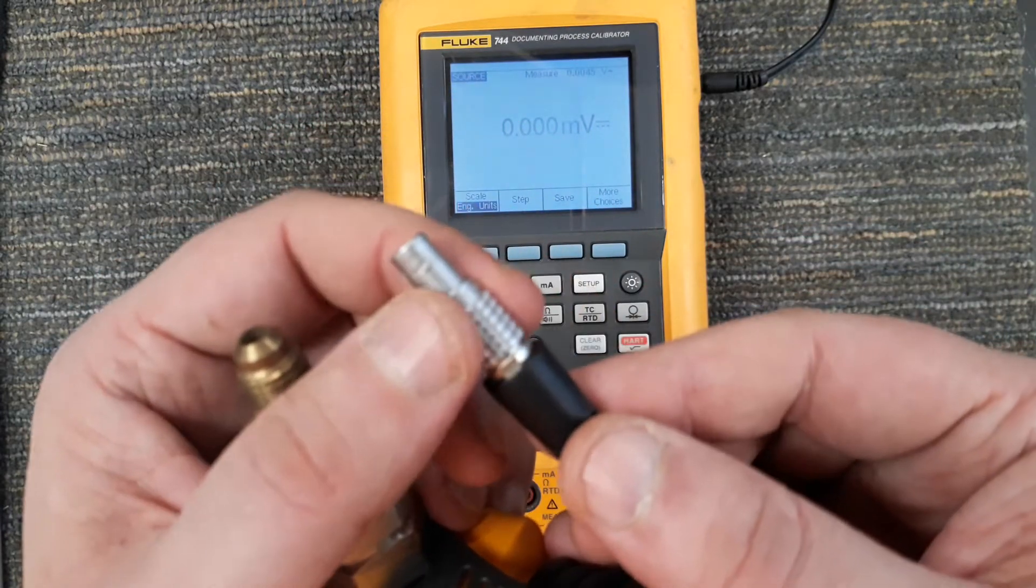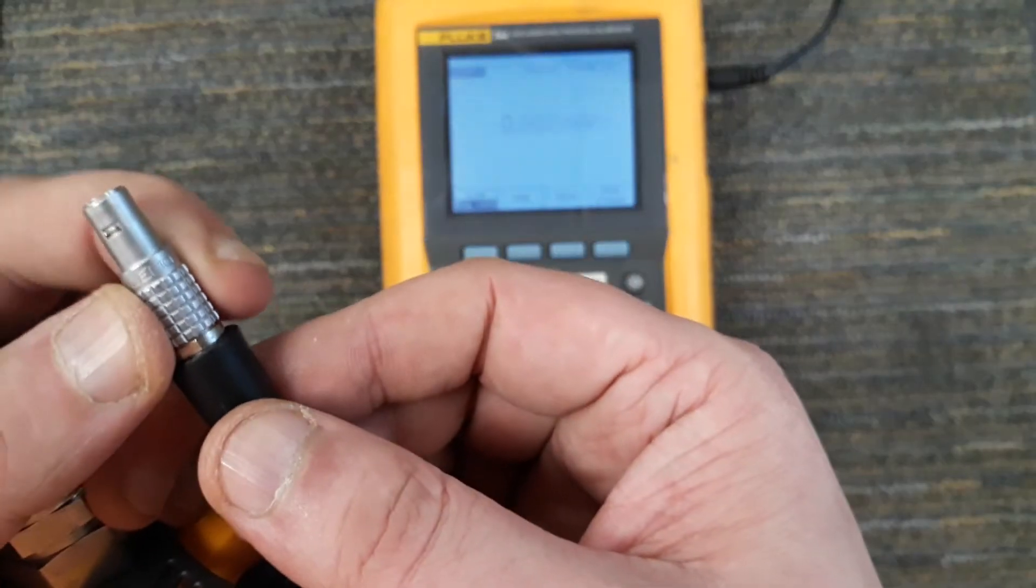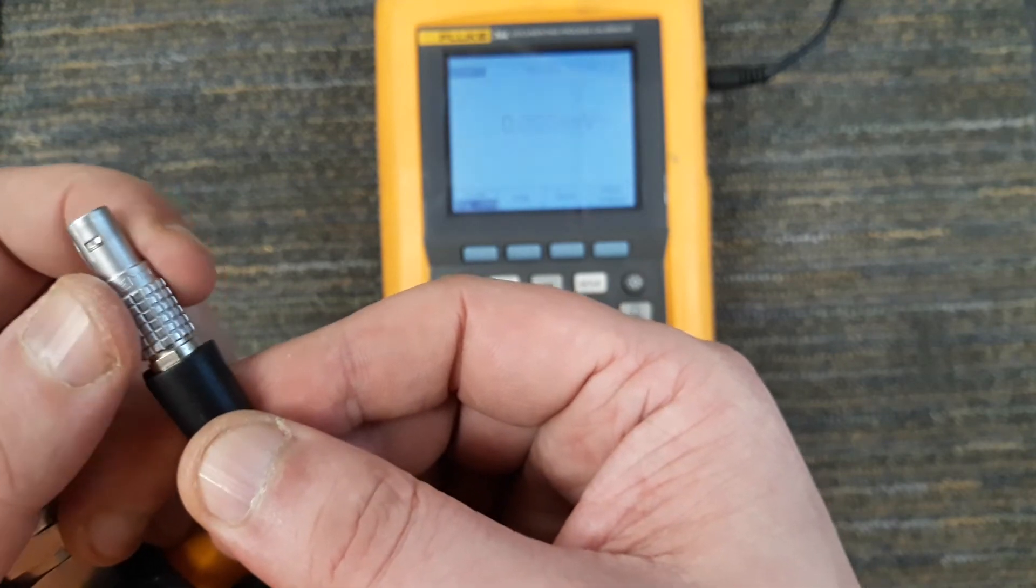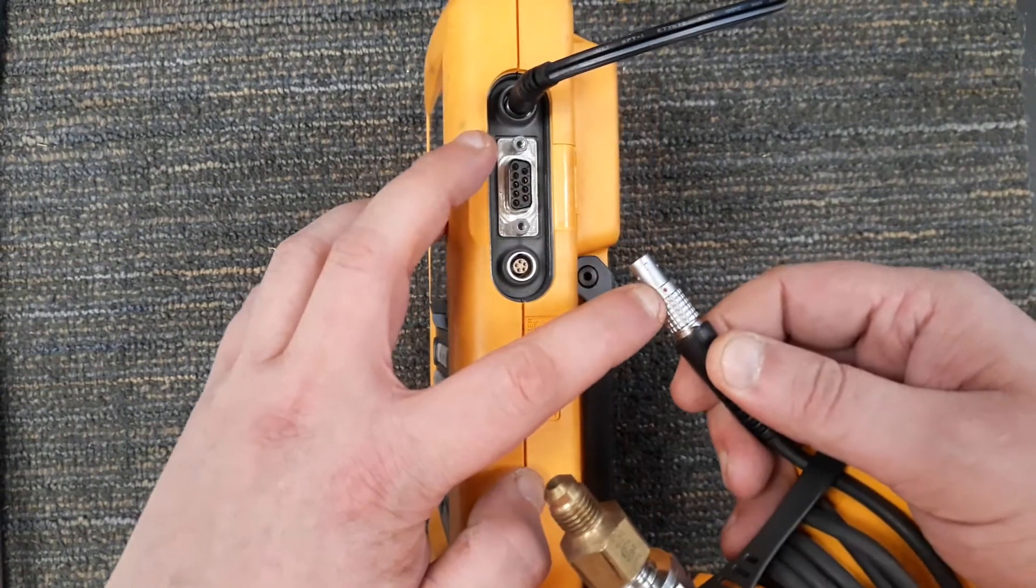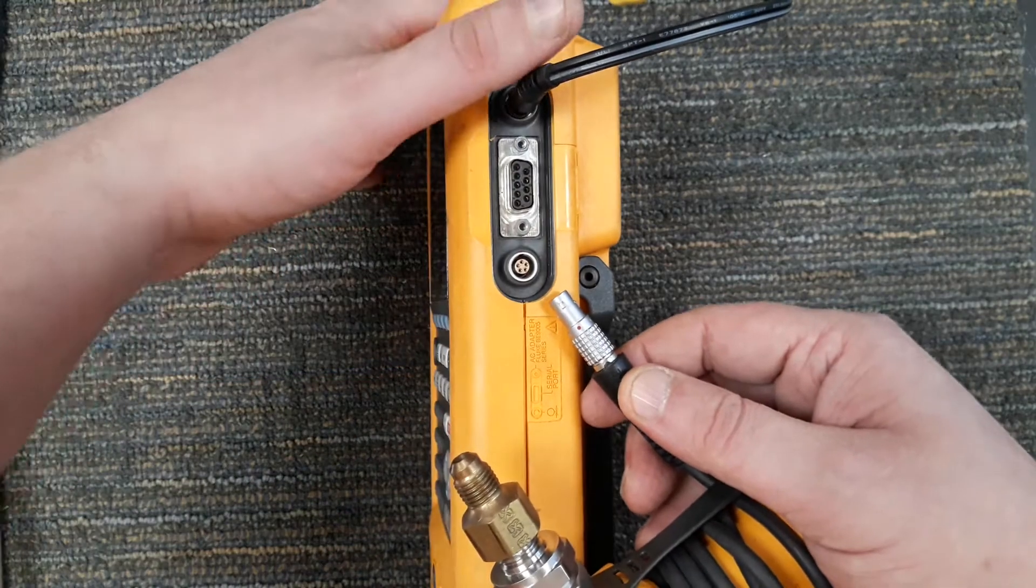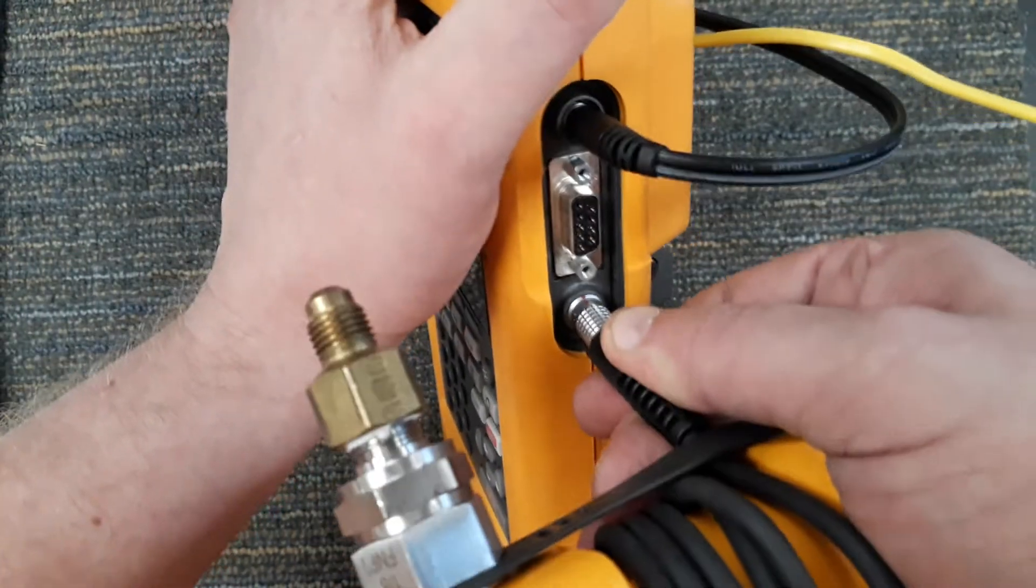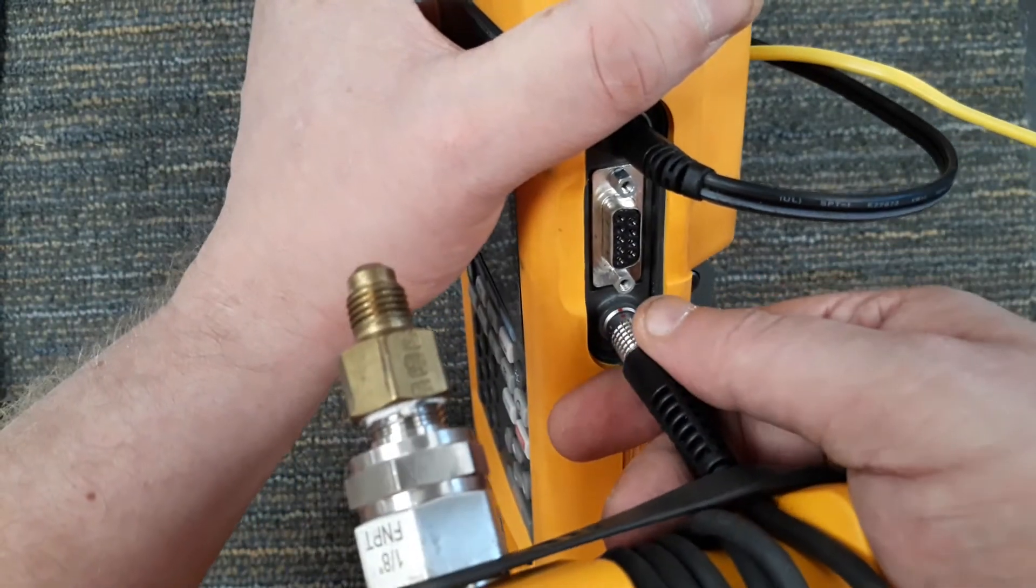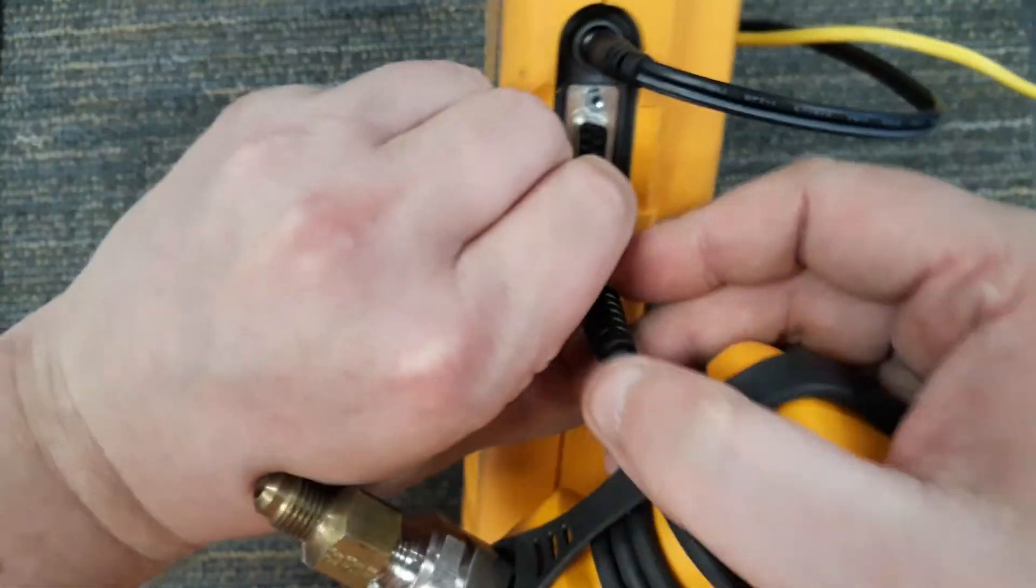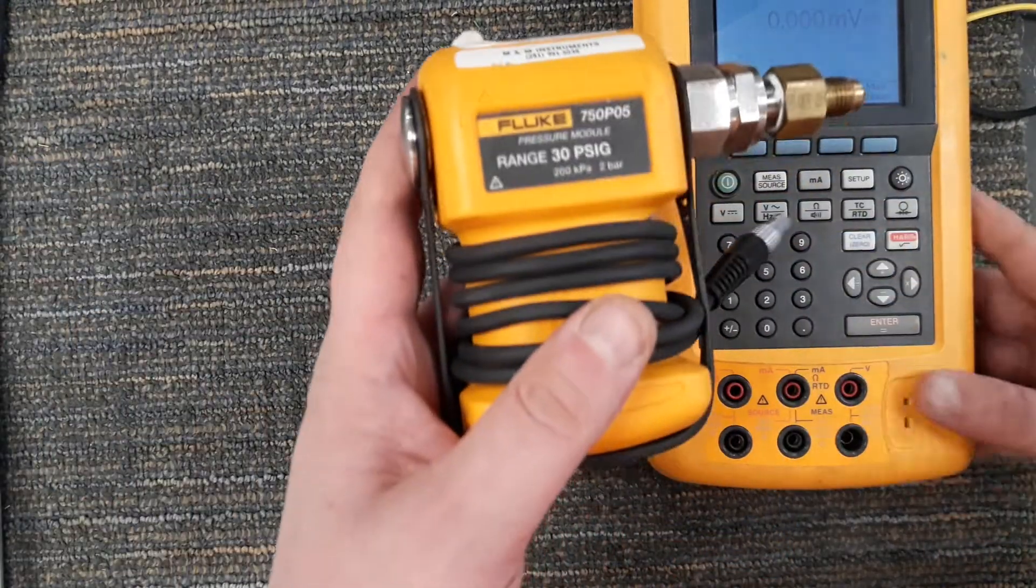It does not screw in, doesn't unscrew. You quite literally, if you look, this sleeve slides and that's what unlocks it, locks it and unlocks it. So if I wanted to put that into the side, I make sure that my red dot on the sleeve lines up with the red dot which is you see the red dot on the top, and I would just plug it in. But notice it won't come out. And a lot of people because it won't come out just pulling on it, they'll try to twist it off. Do not twist these. Reach in there, grab that sleeve, and you slide it - slide the sleeve back and it'll come right out.